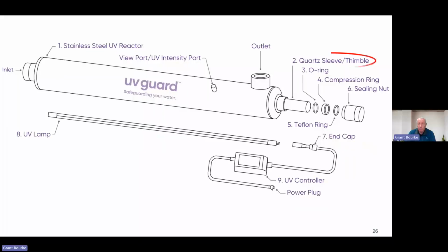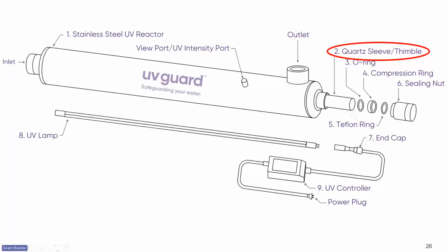Now the lamp sits inside a sleeve, and the sleeve is what's sealing the water away from the lamp. The sleeve is made of quartz and it's transparent. You need to get the sleeve out and check that it hasn't gone horribly opaque, or that it hasn't picked up a whole lot of muck and need cleaning. So the bulbs are replaced annually. You can just replace the bulb, but what you're really supposed to do is get this quartz sleeve out and have a look at it and give it a clean if it needs it.